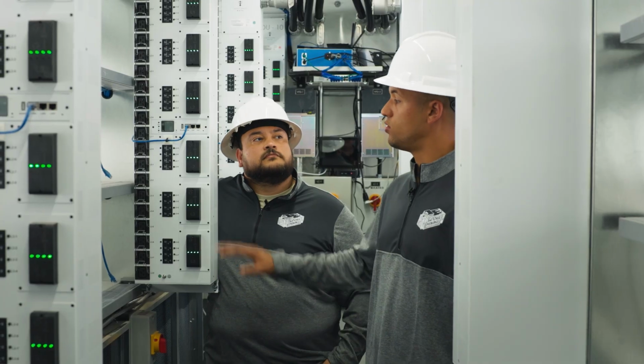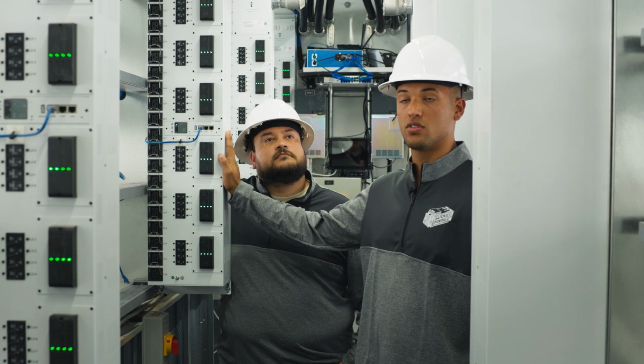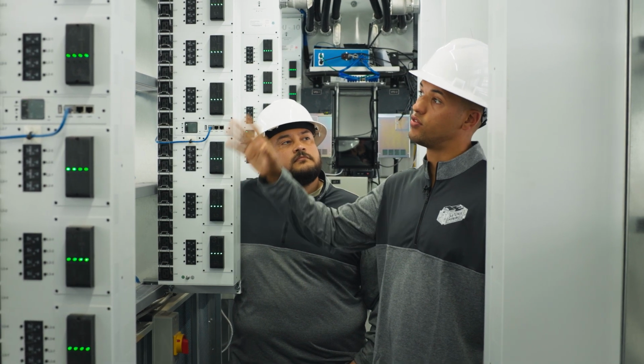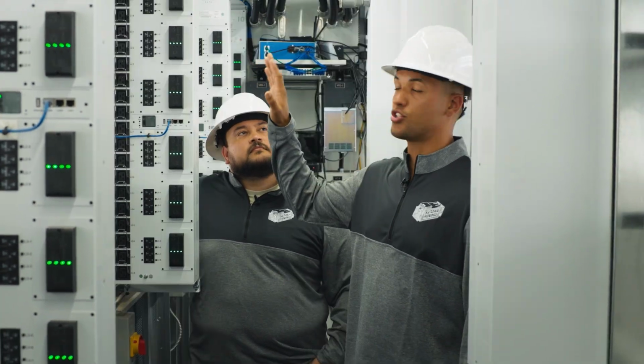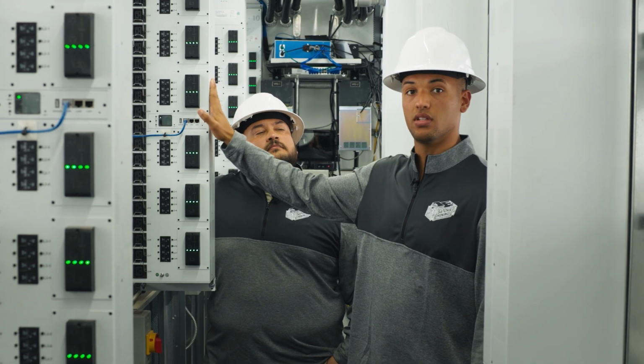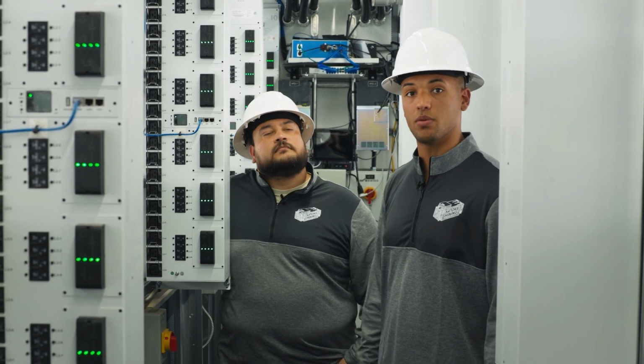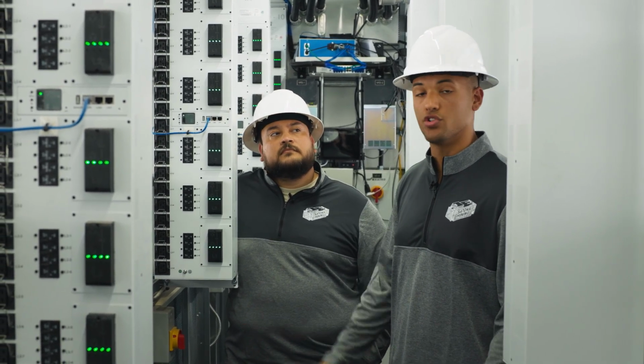So each of these PDUs you see here is rated for 415 volts and steps it down to 240 for the machines to use. In each container, we have 10 PDUs, and they add up to 900 kilowatts total of capacity for this container, so we can run about 240 units.